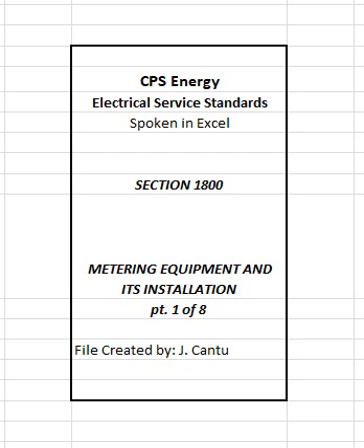C. Wiring of single position, self-contained meter sockets. Customer shall furnish and terminate all conductors within single position, self-contained meter sockets. Exception number 1. Where CPS Energy service lateral conductors enter a meter socket, CPS Energy will make the terminations of these conductors. Exception number 2. Where fifth terminals are required on 3-wire 120/208 volt meters, CPS Energy will make the necessary terminations on the fifth terminal, refer to Figure 1805.